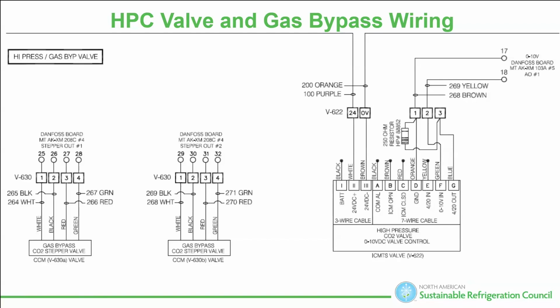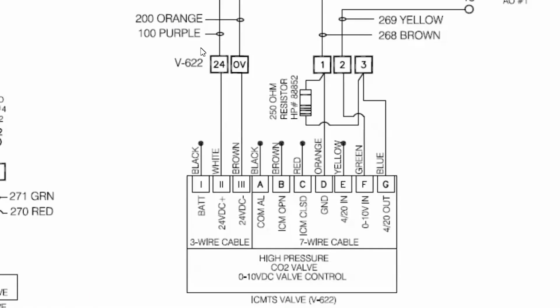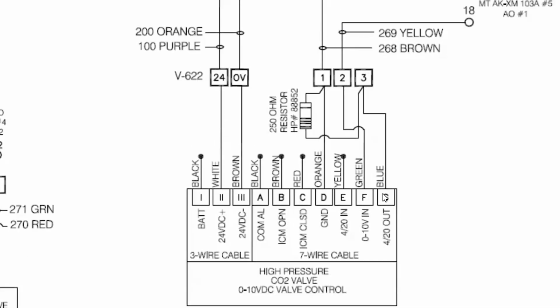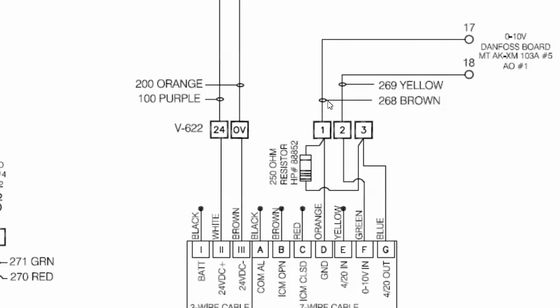It's kind of being replaced with the CCMT valve, but there are still so many of these things around here. So let's see what this thing does. This is the high pressure control valve, the one on the drop leg. I've got 24 volts on the red leg, the power leg coming into it. Now on the black leg, I have a 0 to 10 volt signal coming from my analog output board.